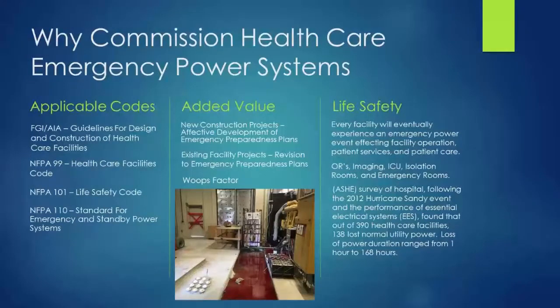So, added value. In new construction projects, when we're talking to clients, why would I do this test? What's the value for them? Well, when our clients get to witness this test or read the reports after we're done, it's going to help them effectively produce their emergency preparedness plans and also develop their methods of procedures for when they have a power outage and are running prolonged on generators. And the same is true for existing facilities. In existing facilities, it might be a little more beneficial, because they can look at their defined emergency preparedness plans and methods of procedures and go back and say, hey, this didn't work. We can redefine it now, because we've actually seen the system operate in a controlled method and seen what it's actually going to do.